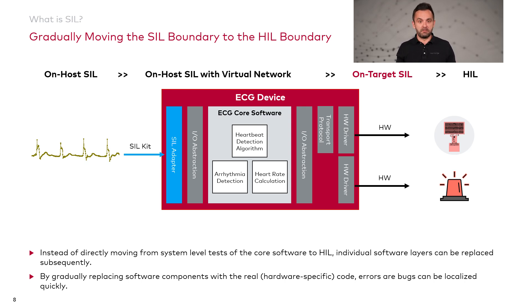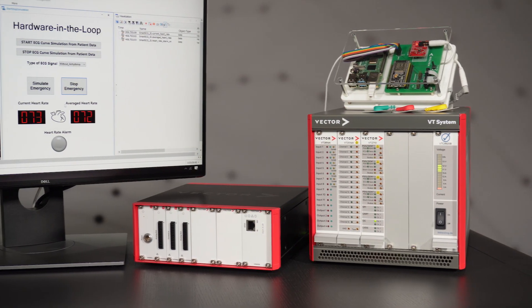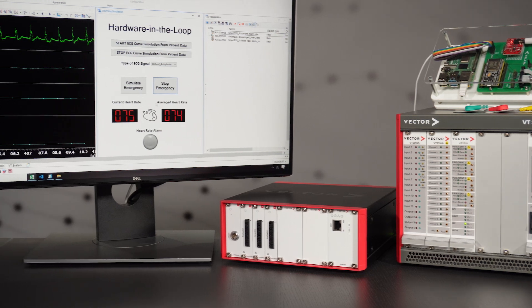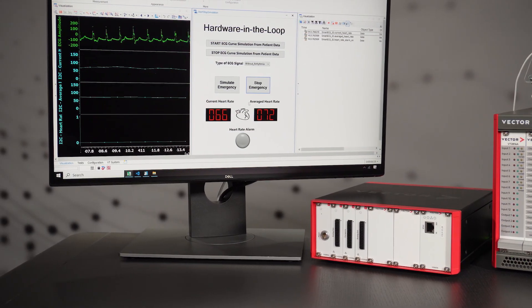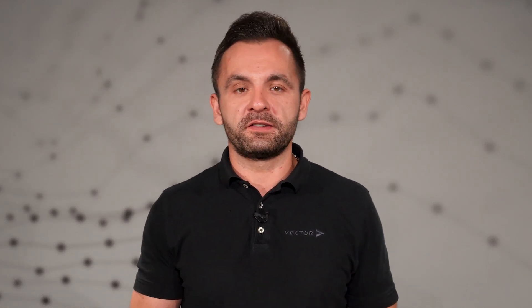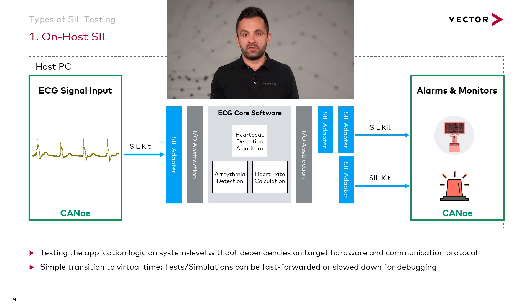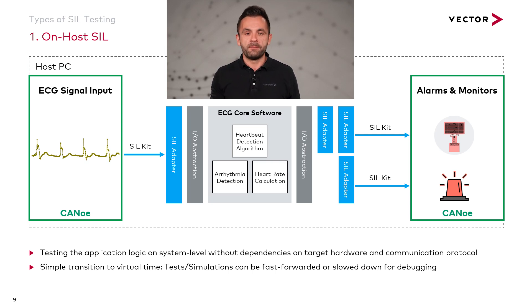The last step of the system level tests is the HIL phase, where you test the whole device with its final software. Now let's take a deeper look into some of the different phases and how they work — for example, the on-host SIL phase. The idea of this phase is to simulate the ECG input signal in CANoe and inject the sensor values virtually into the core software of the running ECG application. Moreover, the alarm actuator and patient monitor that receive the alarm states and heart rates are simulated in CANoe.